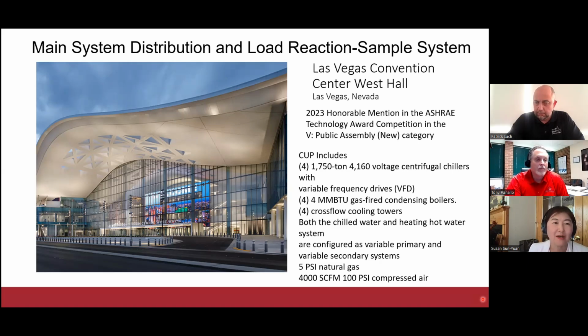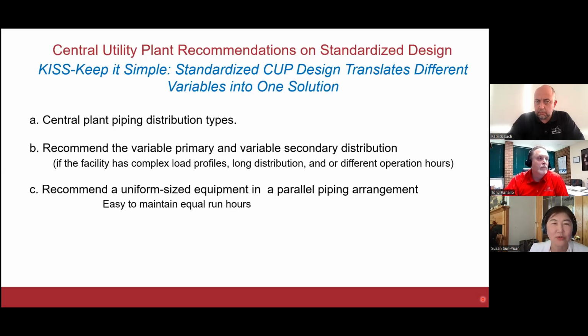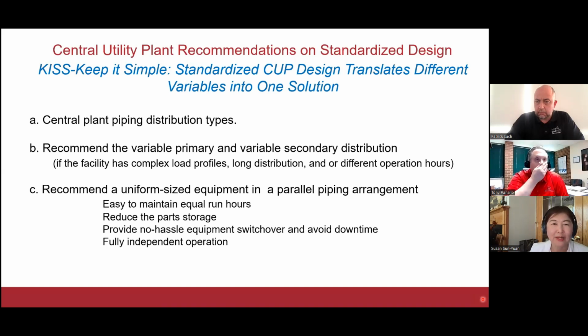The central plant allows us to feel confident without oversizing or adding a redundant chiller, cooling tower, and boiler. As we closely visit the load of each occupancy, the peak coincident load was the basis for finalizing the capacity of the CUP. Next slide, please. There are typically 2 major chill water distribution systems, primary only and conventional primary-secondary system, which means constant primary and variable secondary. Over the past 20 years, numerous ASHRAE, many chiller manufacturers, and other industry publications have provided extensive design guides and case studies on both types.